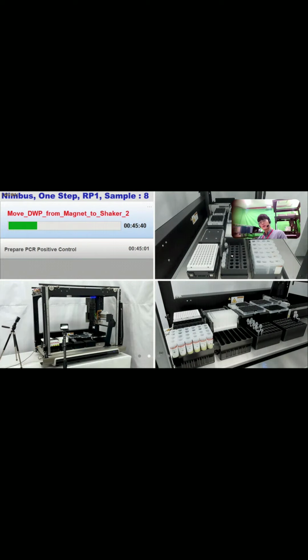as soon as the machine ejects the tip, the machine stops, and put out this deep well plate and also the magnet. The reason the magnet is also put away from the pedestal is that when we measure the volume with the handheld pipette, the beads have to stay in the deep well plate. So that's why we took out both the deep well plate and the magnet.